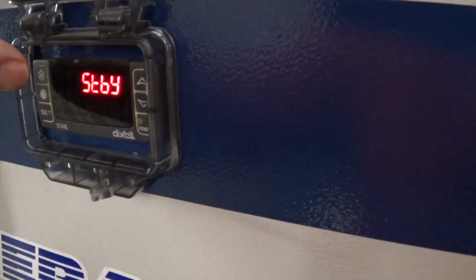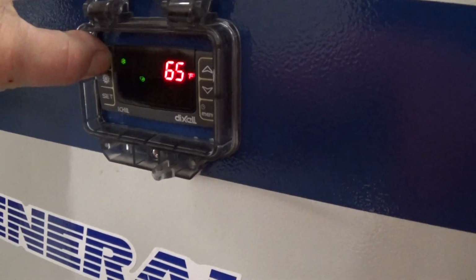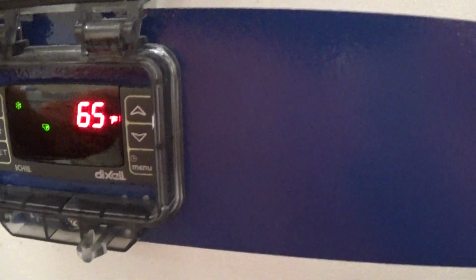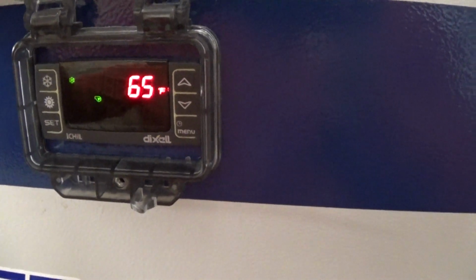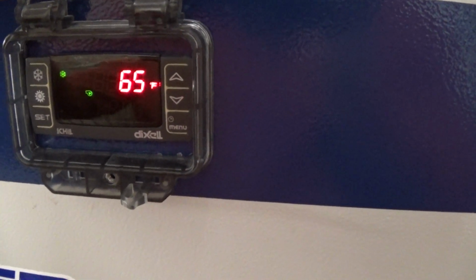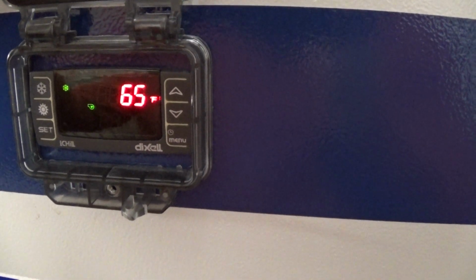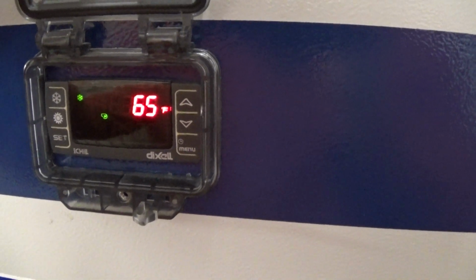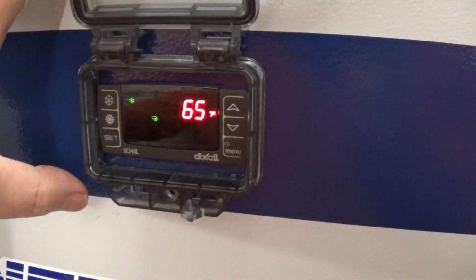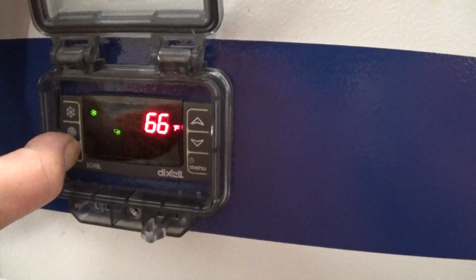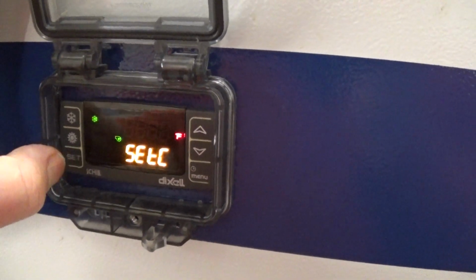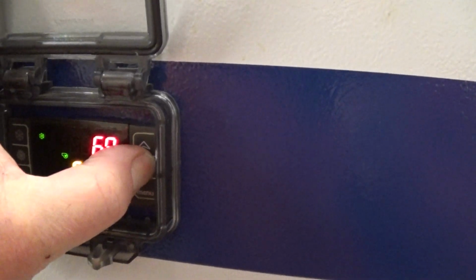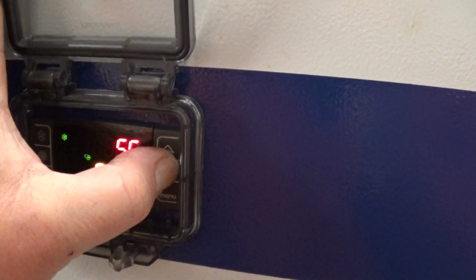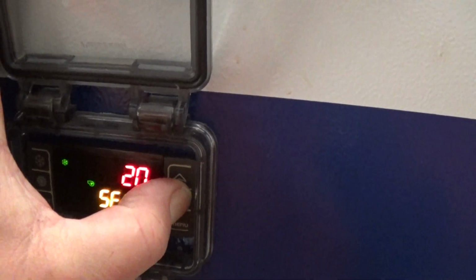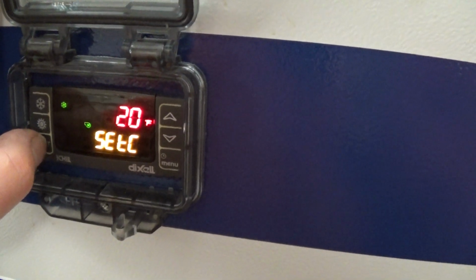So I'm going to take it off standby mode here. And right now you can see we heated up the tank. I say heated, we just ran it up to 65 F, and we're going to run this down to 20 F for a while. We have run it at 20 F for a couple days. To change the set point, I just hold the set button in for 3 seconds. 1, 2, 3. This comes up, and I press the down arrow. I'm just going to leave it pressed down. You have a 20 F limit. I'm going to press set again.